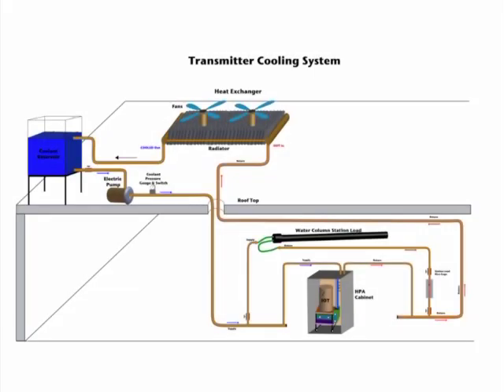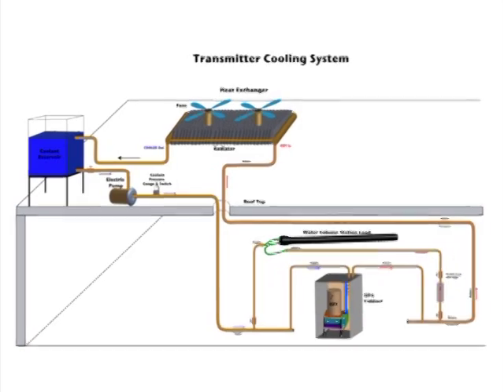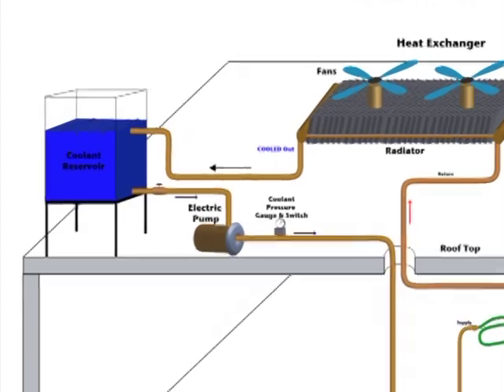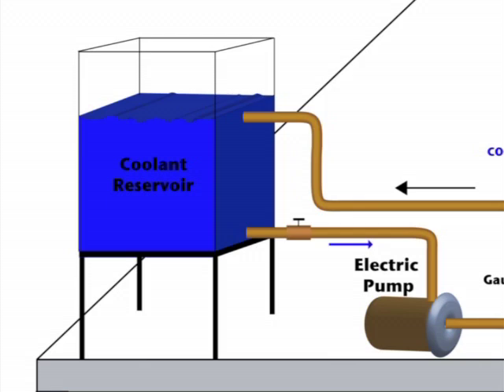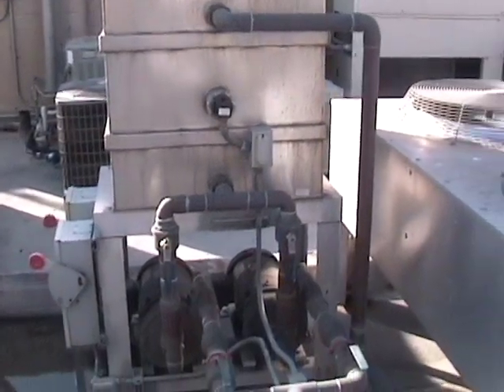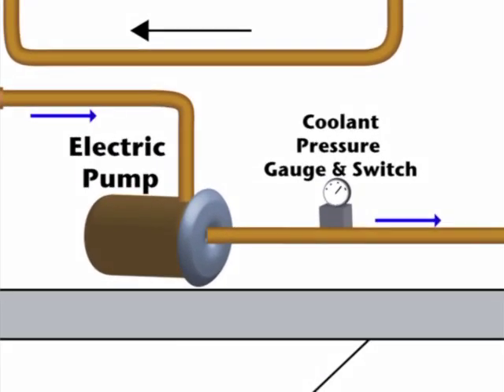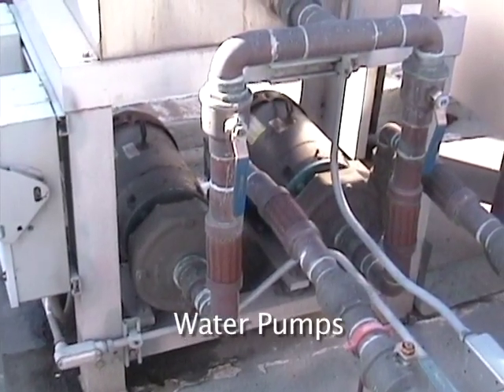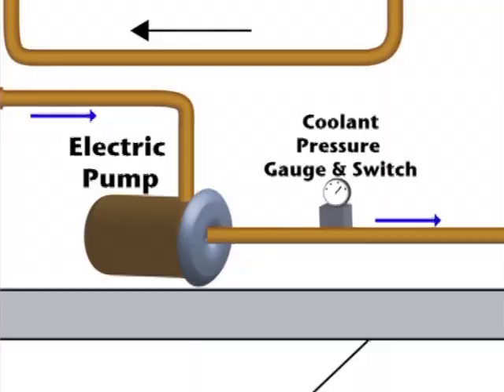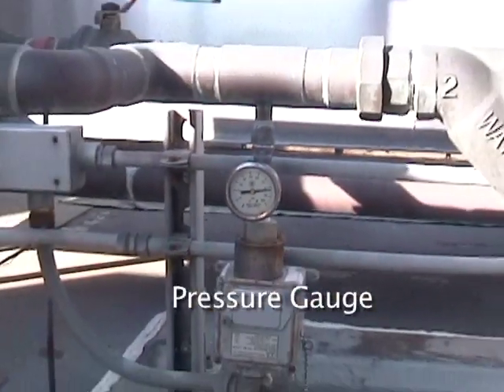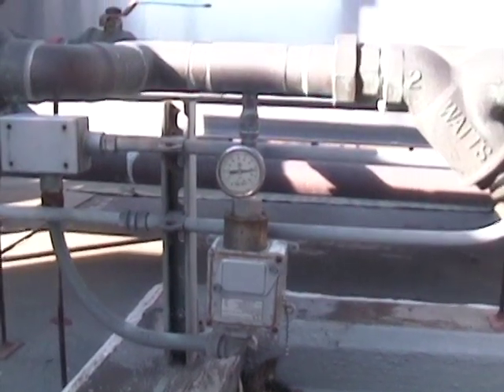The cooling system is a very important part of the transmitter. It removes the heat generated by the high voltages and output powers of the IoT itself. It starts at the reservoir, where the coolant is stored before it is pumped out. A pipe connects the reservoir to an electric pump that pushes the coolant through the entire system. Here you can see an actual reservoir connected to the two pumps below — one is always on standby. The two water pumps are used alternately to ensure that one is always working. After this is a pressure gauge and pressure switch, which informs the transmitter if the coolant stops and will turn off the transmitter if need be.